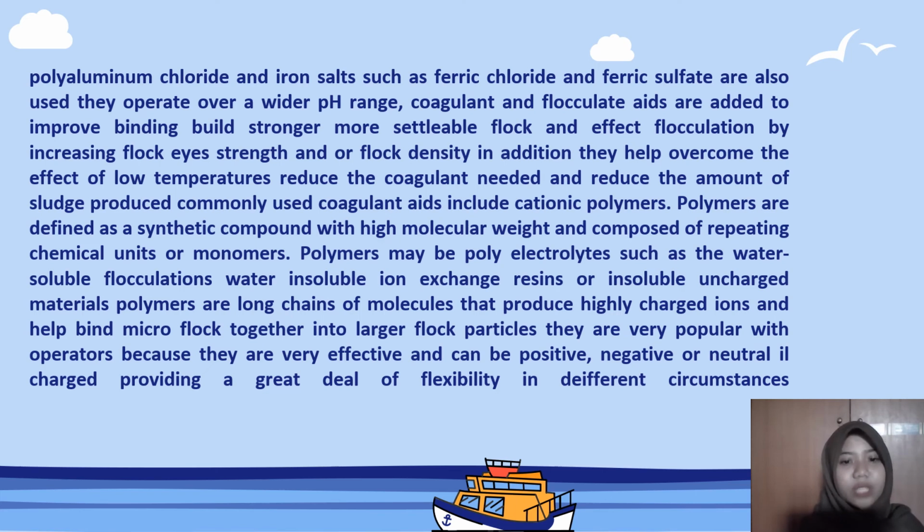Polymers are long chains of molecules that produce highly charged ions and help bind microfloc together into larger floc particles. They are very popular with operators because they are very effective and can be positive, negative, or neutral ion charged, providing a great deal of flexibility in different circumstances.